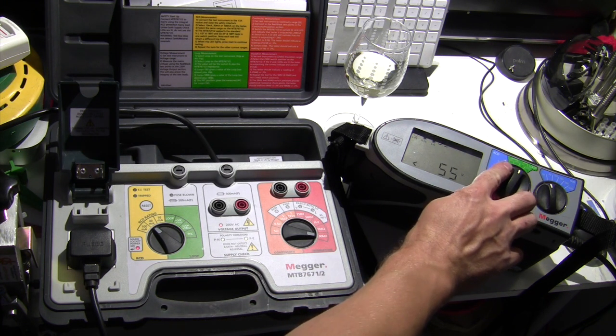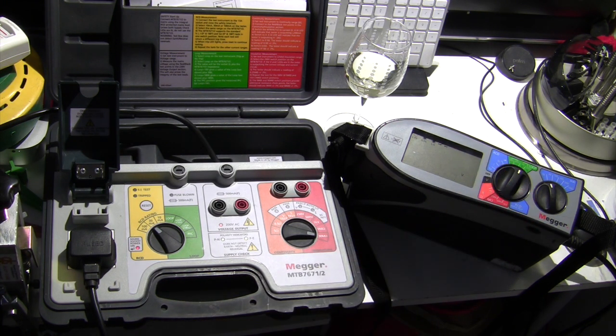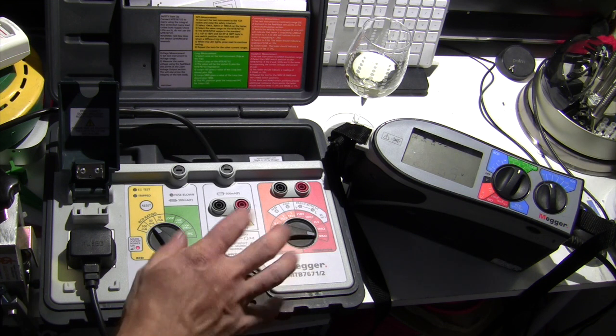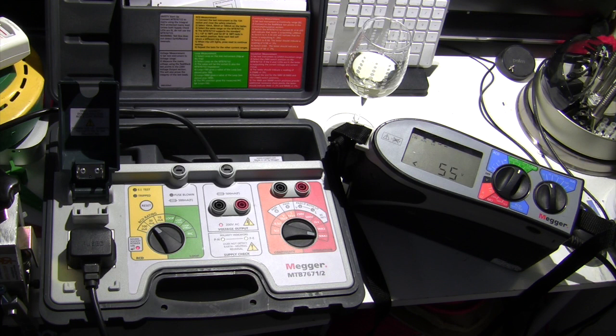To the left of that we have the same tests, but this time it brings in the neutral on the no trip and the prospective fault for the earth fault loop impedance and prospective fault current. So you'd use those tests on the left side there if you were testing a circuit with an RCD on. Again, it's a moot point here because although there is an RCD on this circuit, this thing is going to intercept any nasties and not send anything down the line to trouble that.